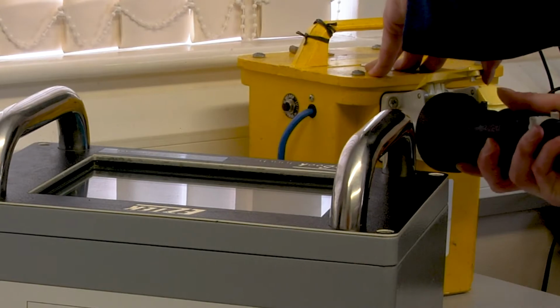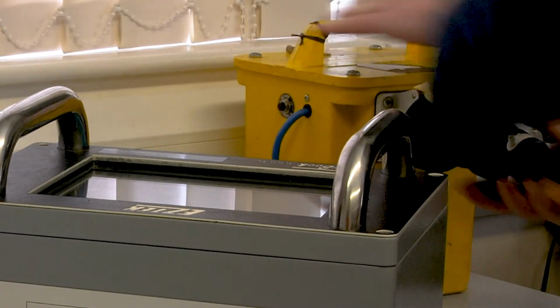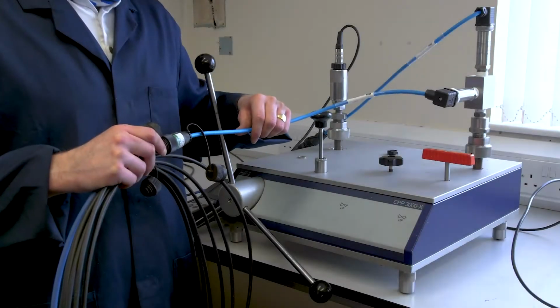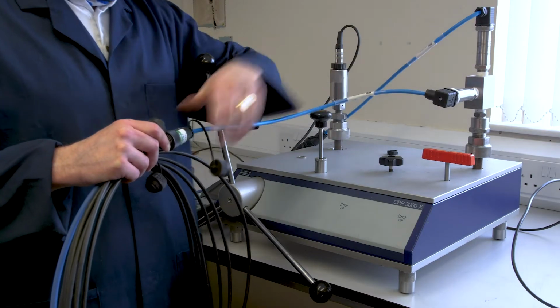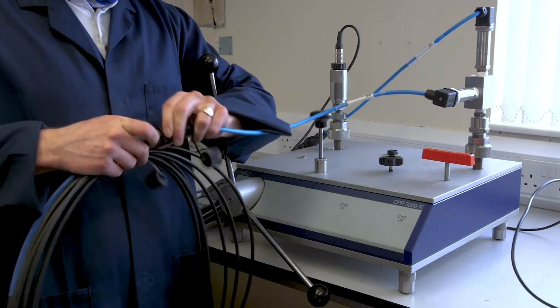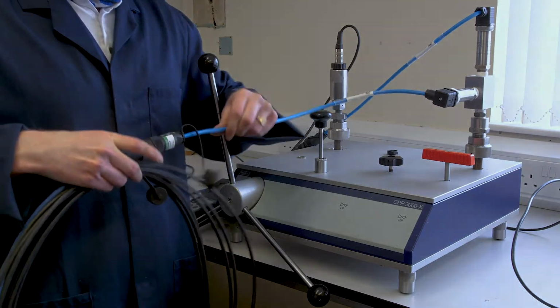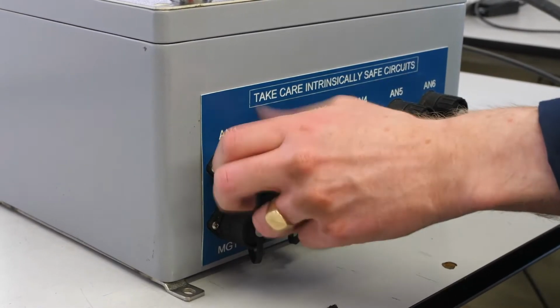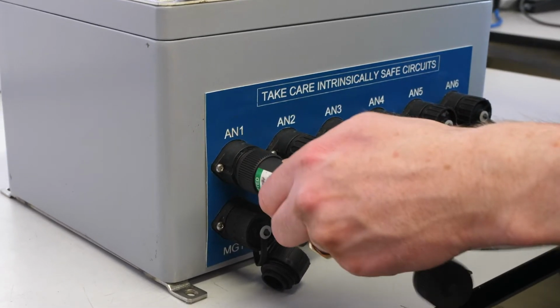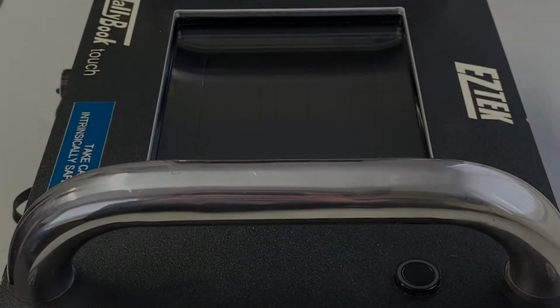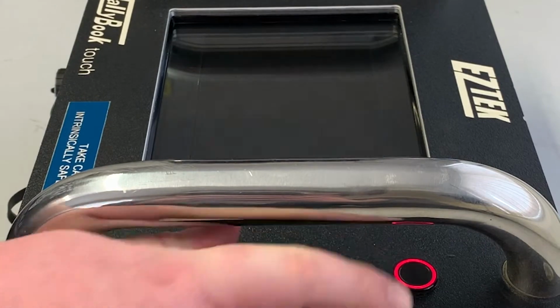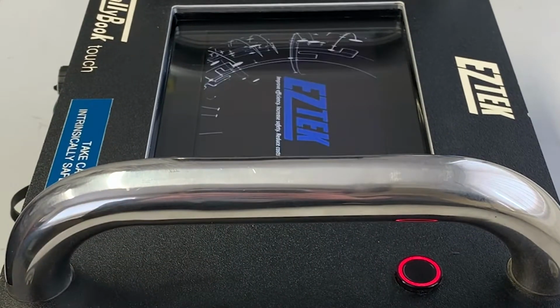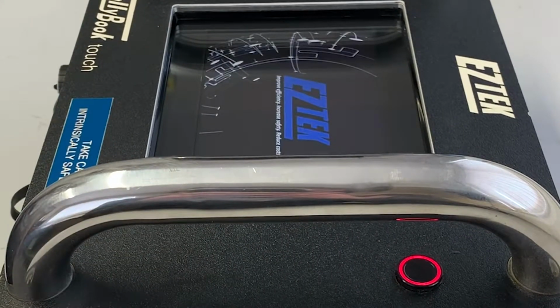Once the power supply has been connected, we can then proceed to connect the transducer cable between the TallyBook and test equipment. In this instance, we have a transducer already in place on the testing equipment, which we will connect back to the TallyBook in the port connector labeled AN1. To start, we switch the unit on, and then use the touchscreen to start monitoring and recording the test.